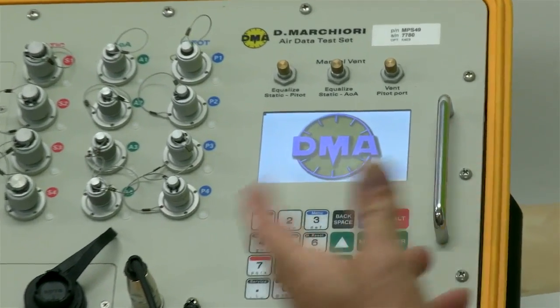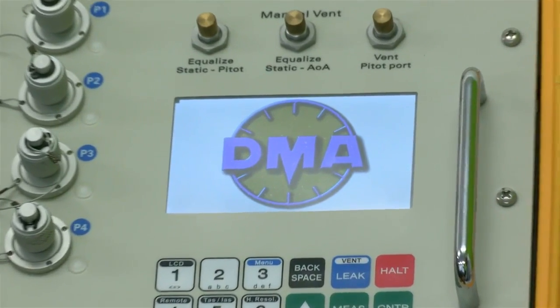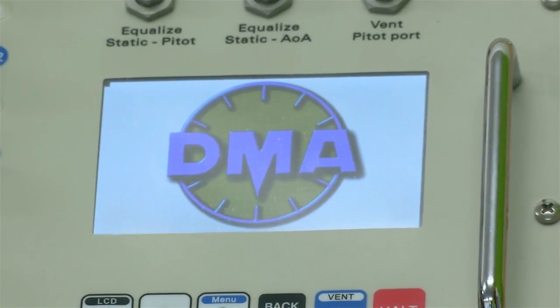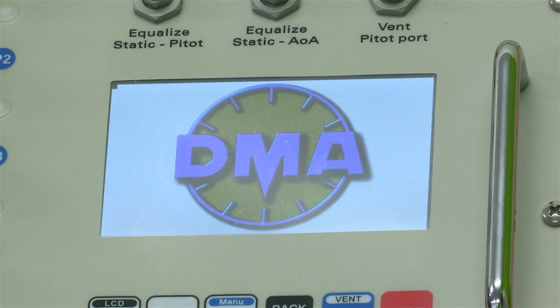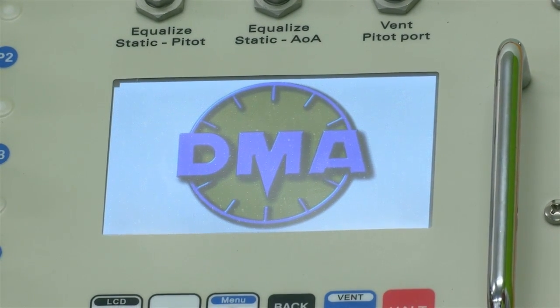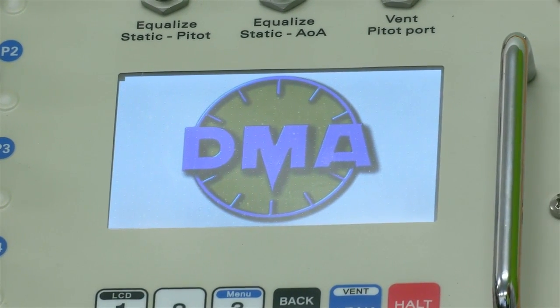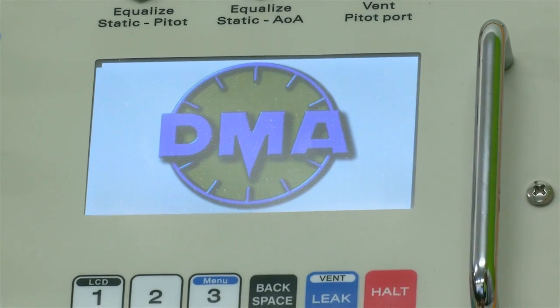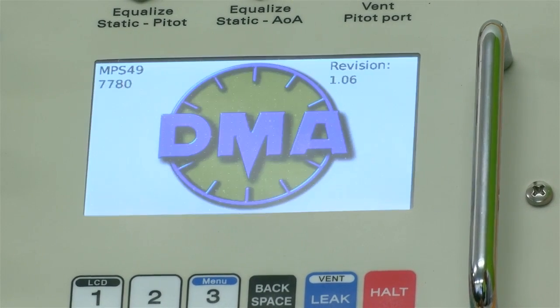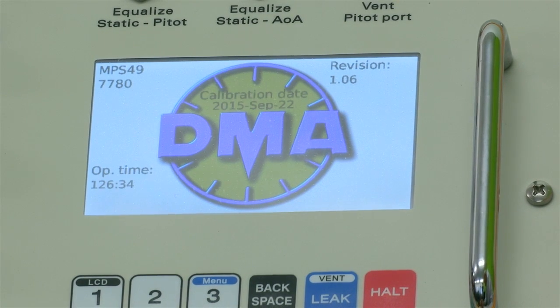We'll show how many running hours there have been for the internal pumps, and then we'll go through a startup procedure in terms of taking the instrument down to safe ambient values before we start. Well, we almost do. We have three different startup procedures. One, it will come straight online if we have a situation where we're very close to ambient.